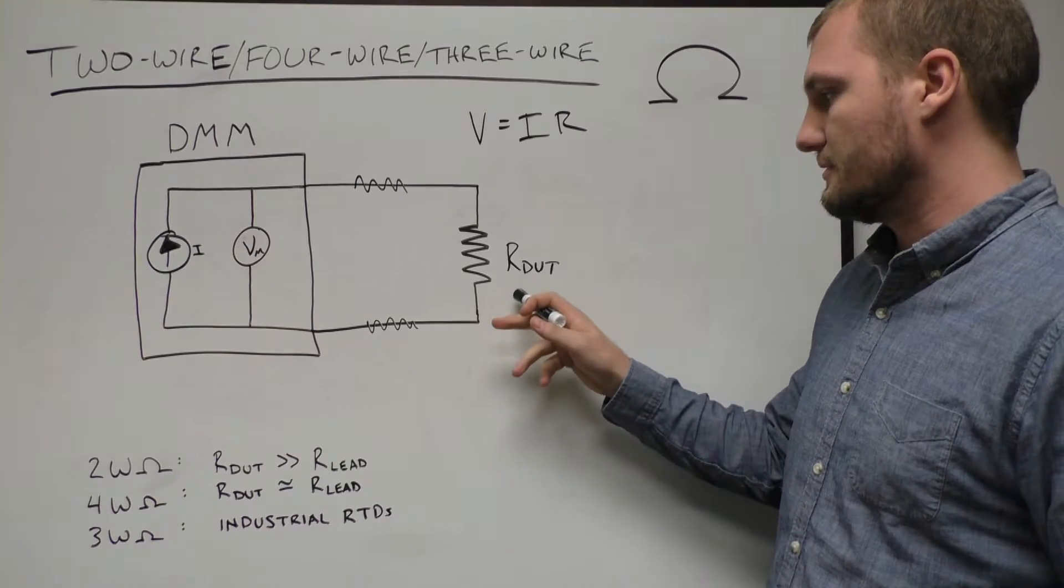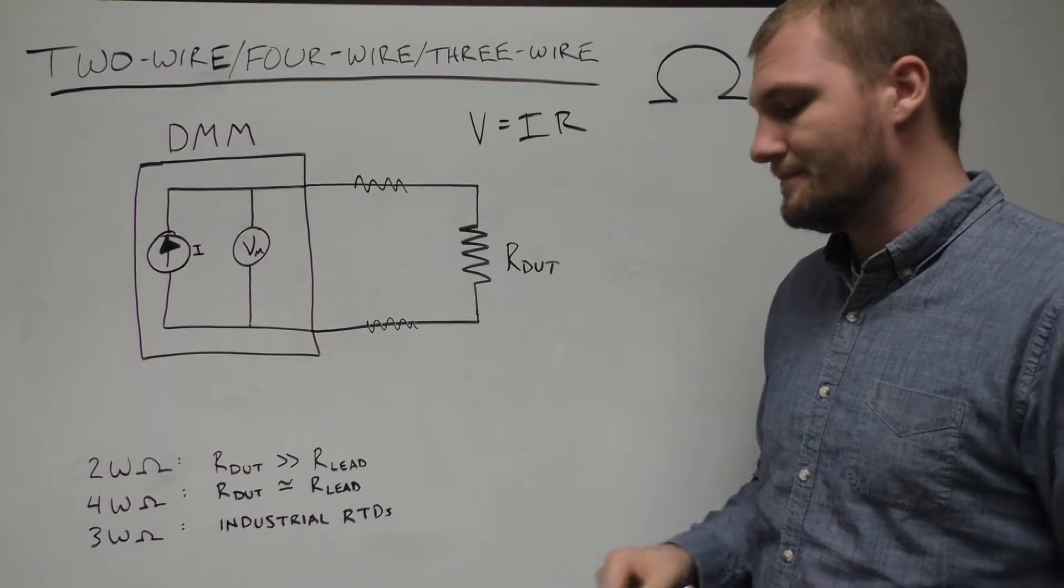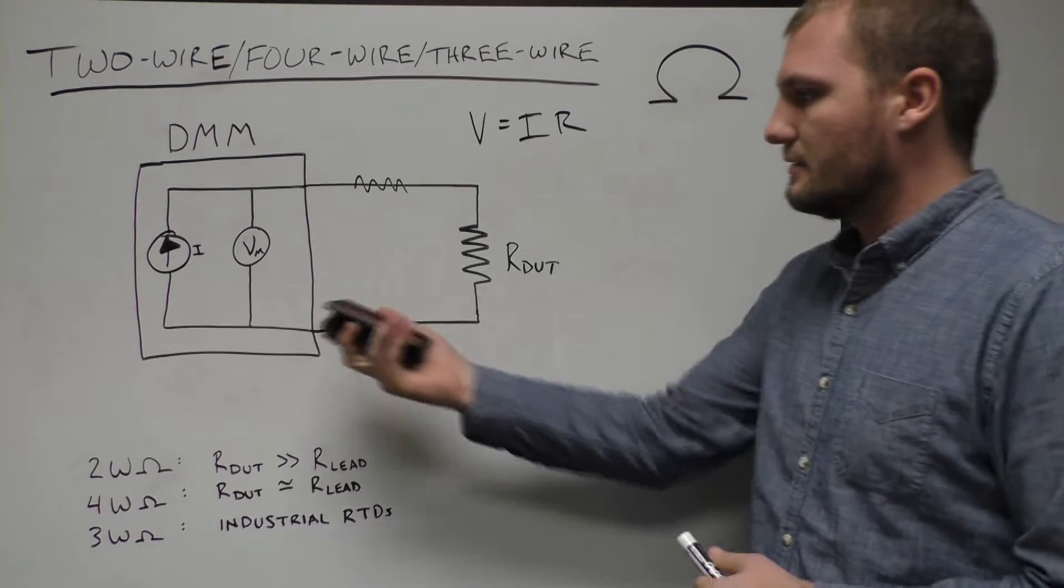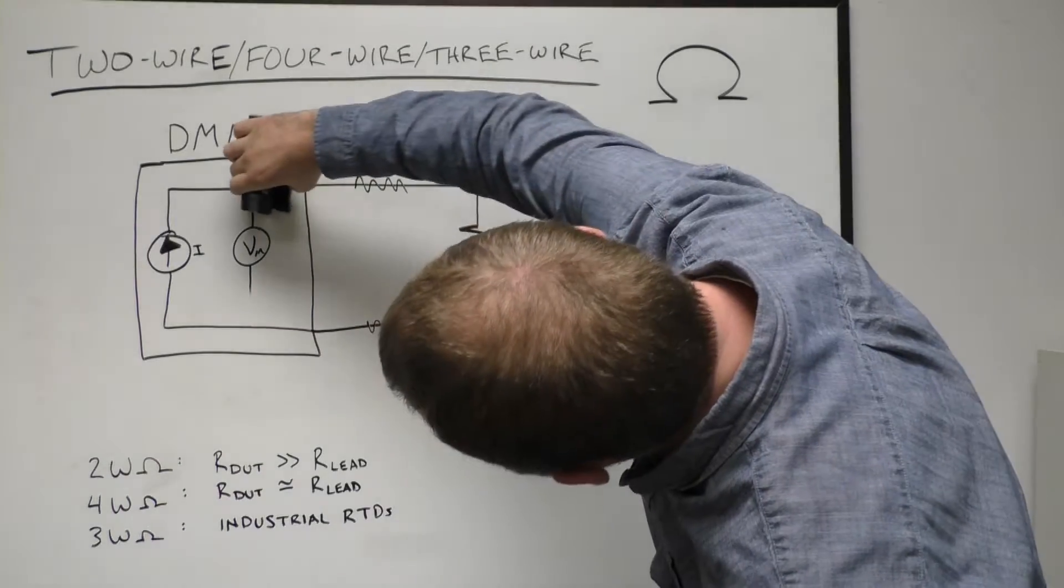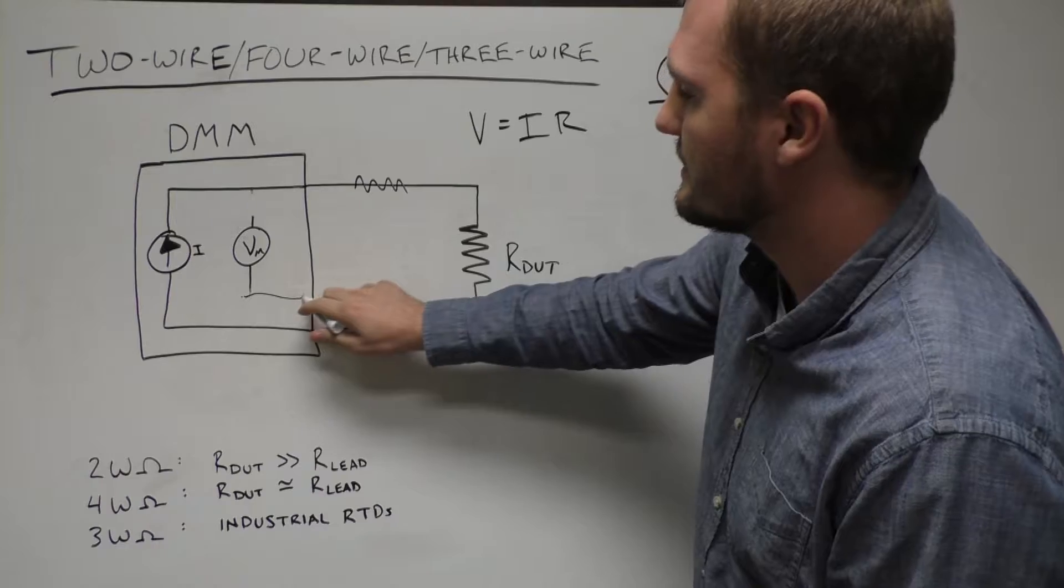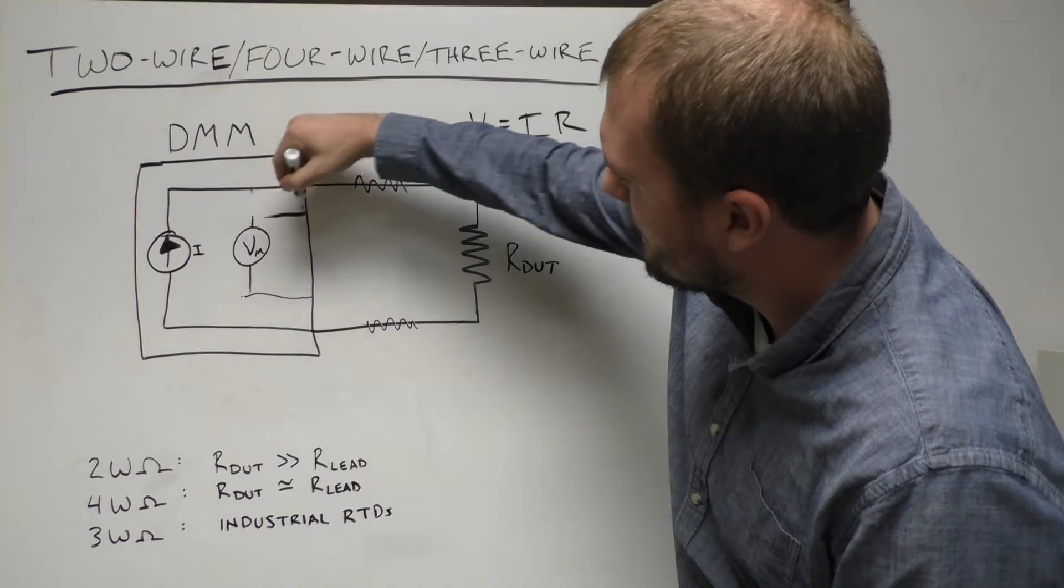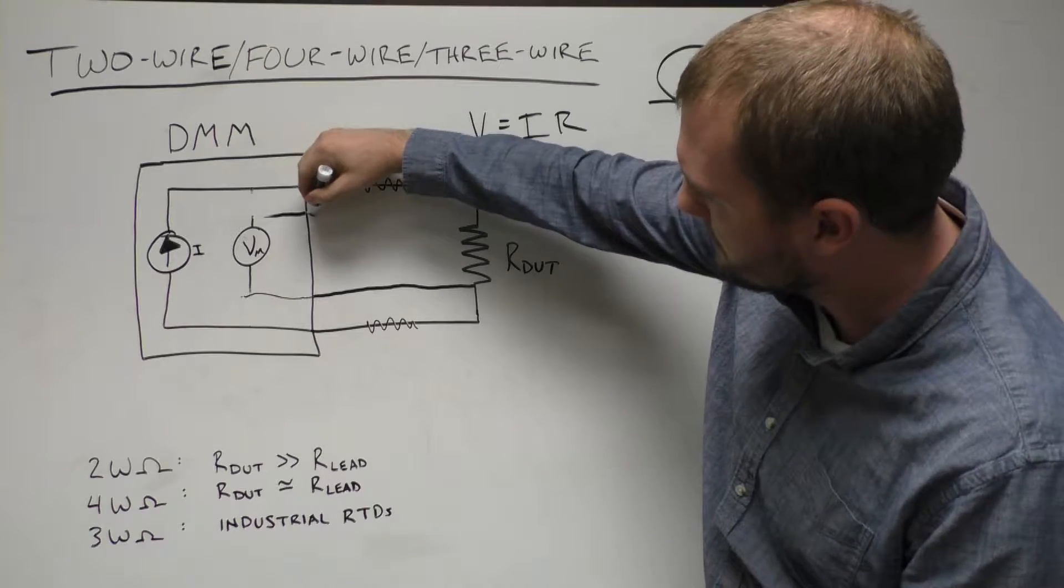Now, if you are measuring a lower resistance DUT, you would want to use something like 4-wire, and in that method, we take the voltmeter and we break it off and put it on its own separate set of what we call sense leads. And these sense leads are attached as close as possible to the device under test.